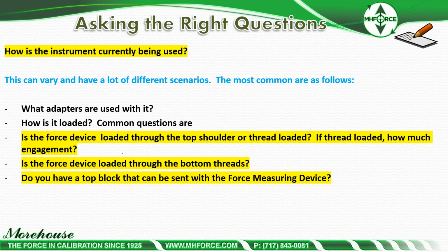How is the instrument currently being used? I haven't seen many people give guidance on this, but this has a lot of impact. This can have a lot of different scenarios. And the most common are what adapters, here's more questions. What adapters are used with it? How is it loaded? Is the force device loaded through the top shoulder or thread loaded? If loaded, how much engagement? Is the force device loaded through the bottom threads? Do you have a top block that can be sent with the measuring device?